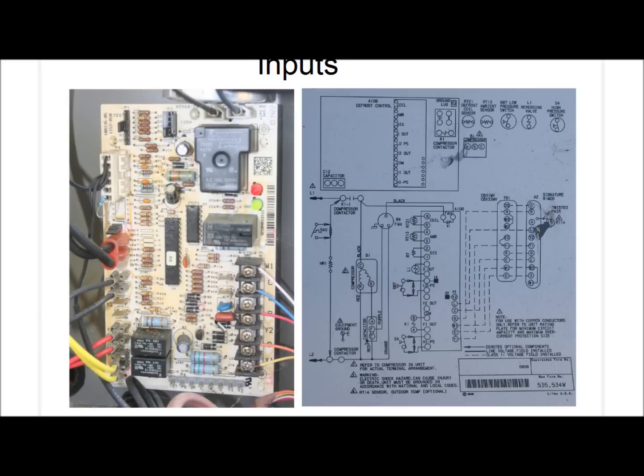Because throughout the years, if there's been any repairs on the control wiring, or if you have an installer that does it differently, you may not have a yellow wire on the Y terminal or an orange wire on the O terminal. So just make sure when you're talking about the connections and the control wiring that you're talking about the terminal designators and not the wire colors themselves.